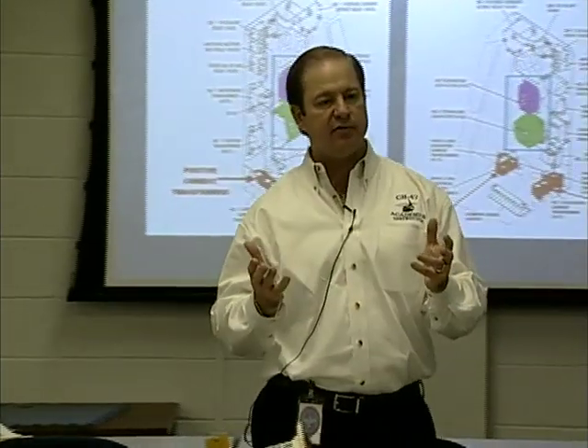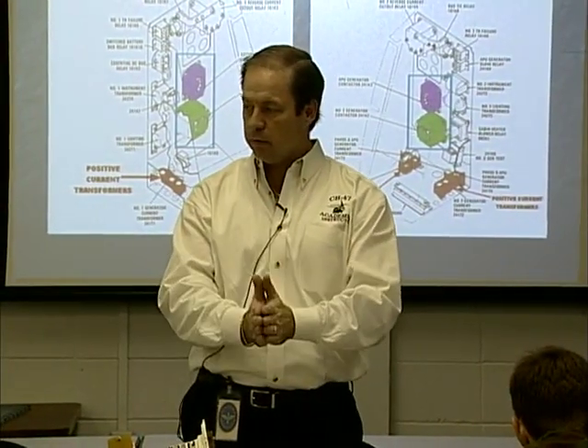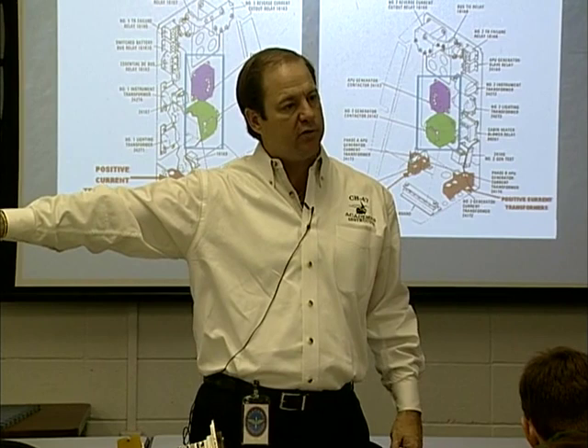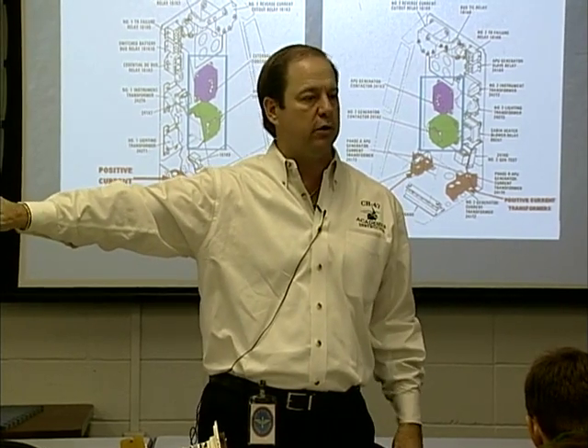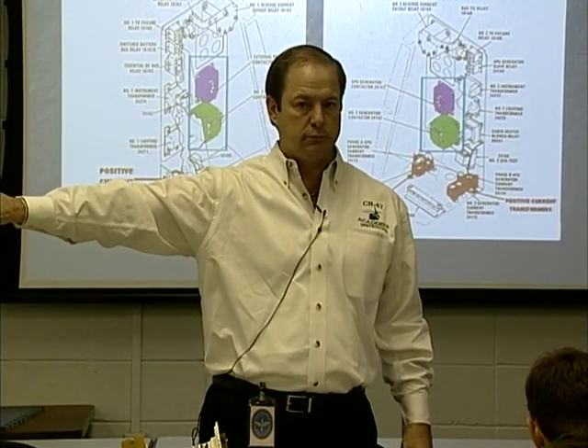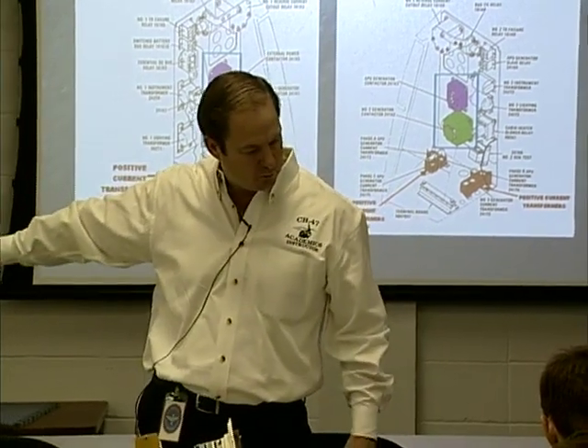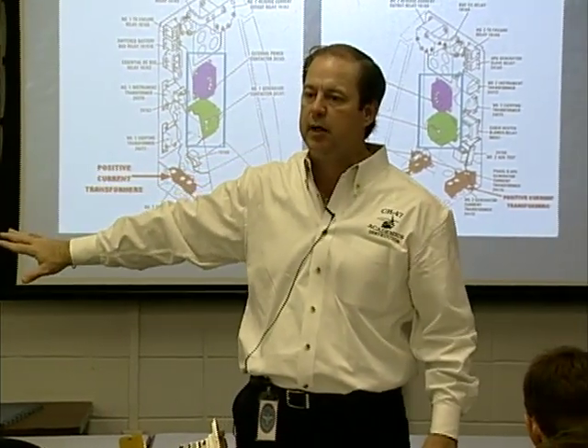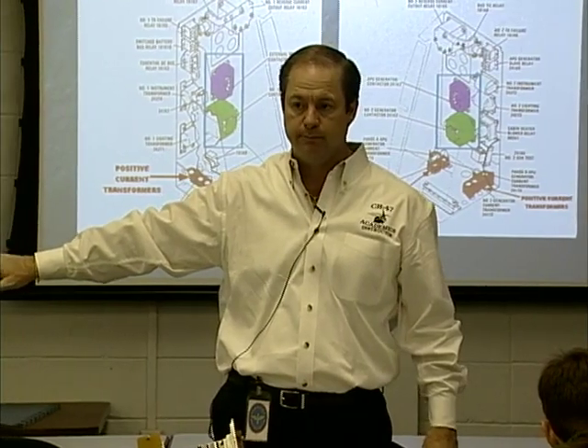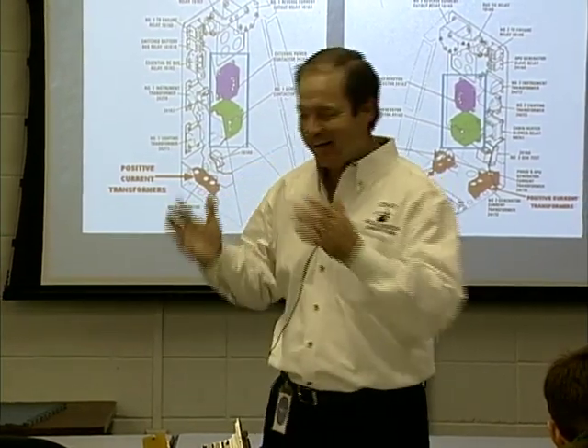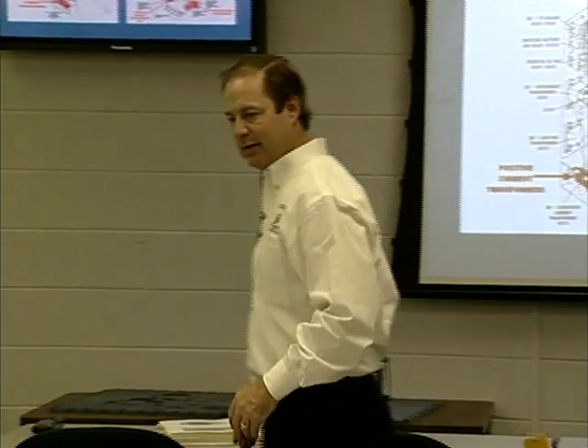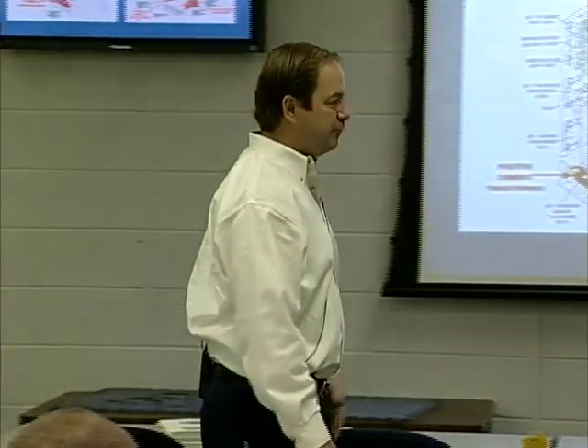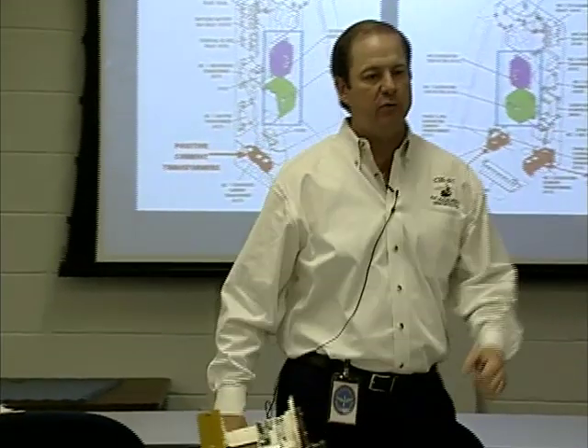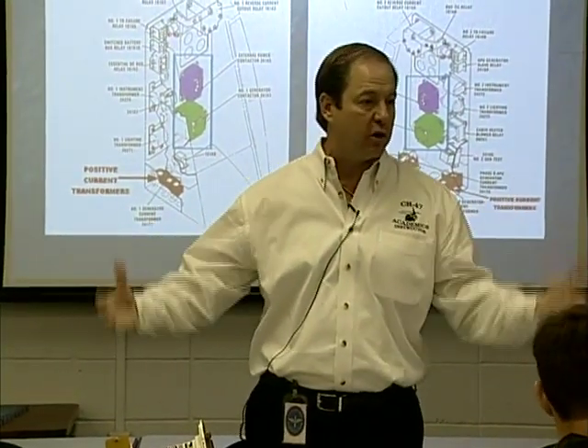Now, how is that allowed to occur? Because the automatic bus tie system is no longer in the picture, if the problem was in the number 2 system, then the chances are I may be able to get the number 1 generator back online. If the problem was in the number 1 system, I may be able to get the number 2 generator online. And keep in mind, because electricity is flaky and unpredictable, we don't know if it was just a power spike or surge.